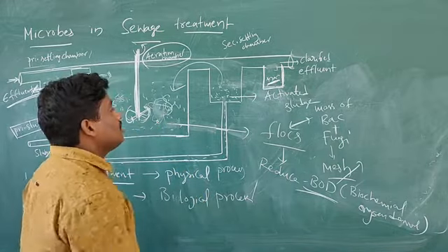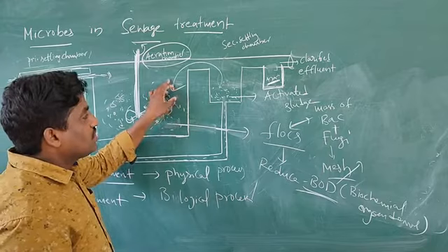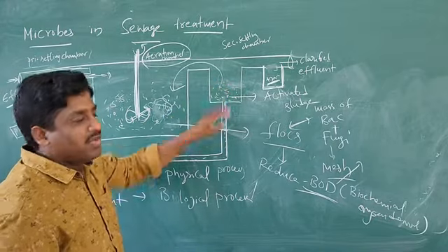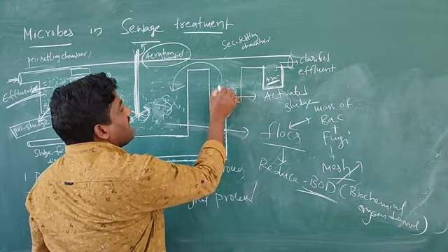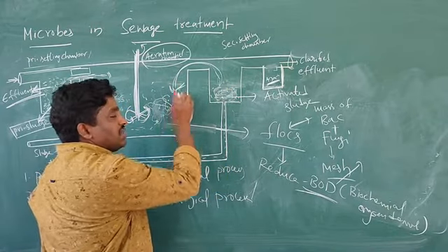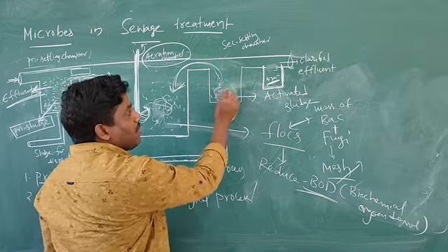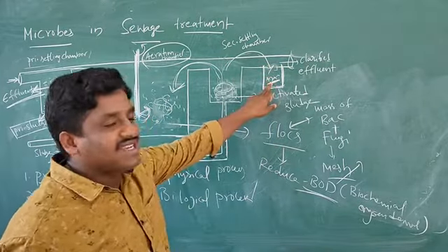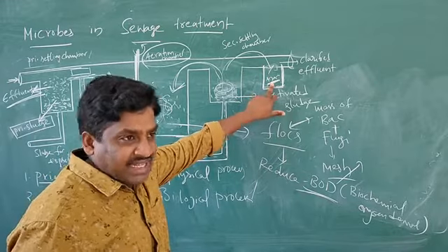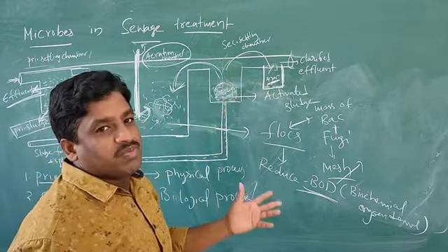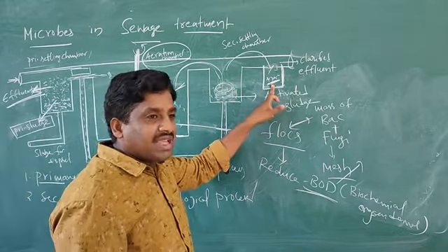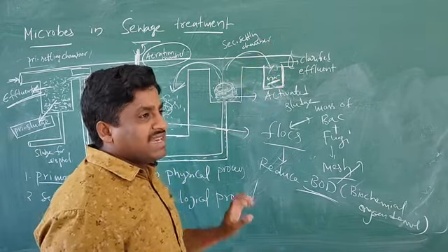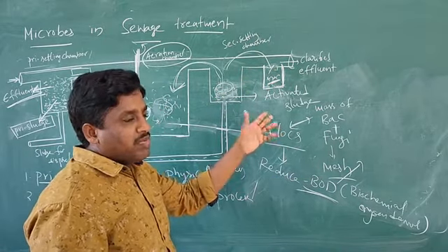Once again, in summary: the primary effluents are transferred into a secondary settling tank, where the bacterial flocs sediment. Some amount of the sediment is transferred into an aeration tank, called inoculum, and the remaining activated sludge is pumped into anaerobic sludge digesters. The anaerobic sludge digesters contain anaerobic bacteria, and the sludge already contains flocs, that means aerobic bacteria. The anaerobic bacteria digest these other bacteria, the aerobic bacteria, that means flocs.